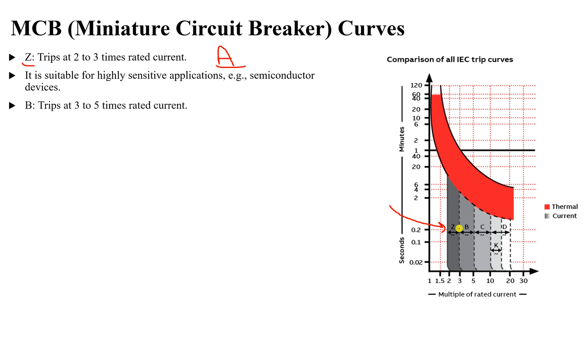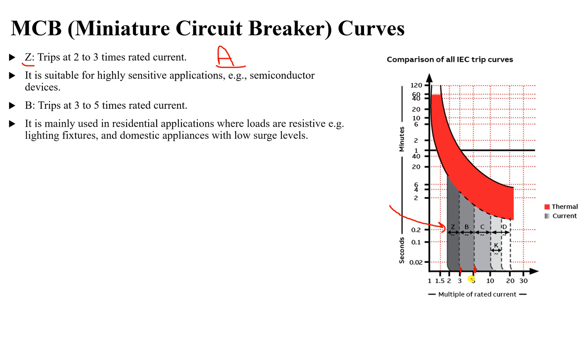Type B starts tripping instantaneously from 3 to 5 times the rated current — this is the IEC-defined range for B. It can be 3, 4, or 5 times depending on the circuit breaker design and manufacturer. This type is used in residential applications where loads are resistive, such as lighting fixtures and domestic appliances with low surge levels.